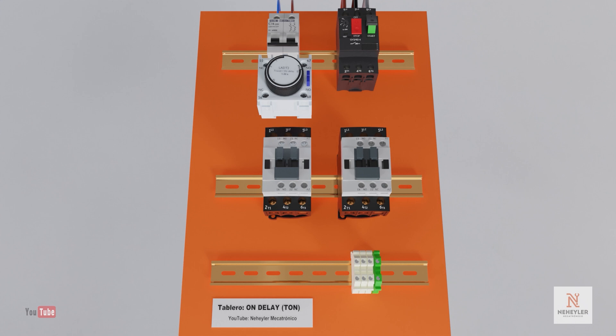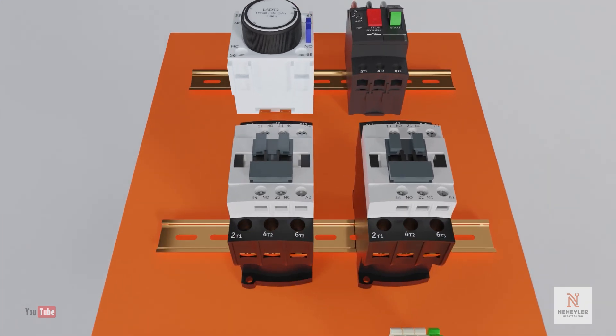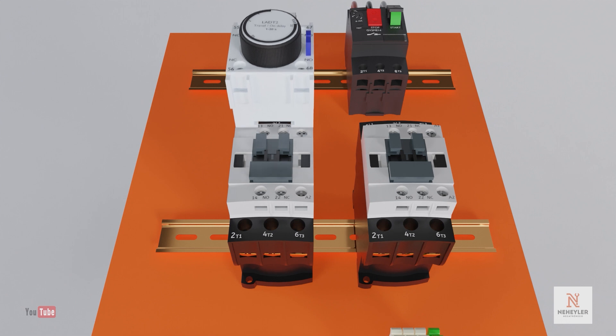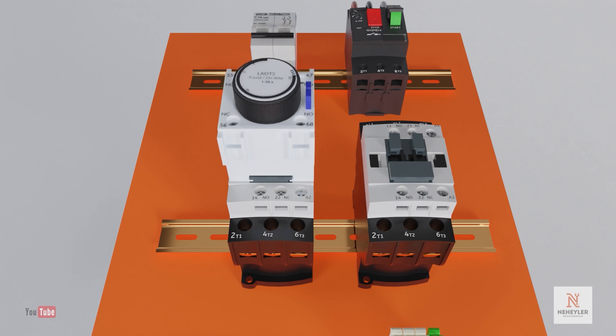As mentioned from the beginning, this type of pneumatic timer requires a contactor so that it can pull and retract the latch. In a contactor, there are slots on the front, in which the timer block is placed. This device is placed over the contactor and slides into the slots until the latch engages with the contactor holder.